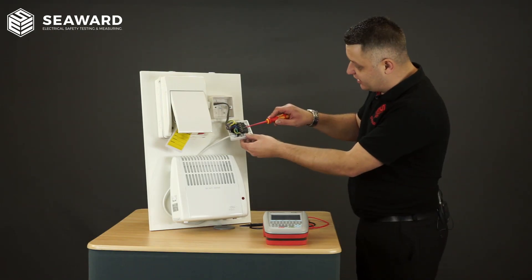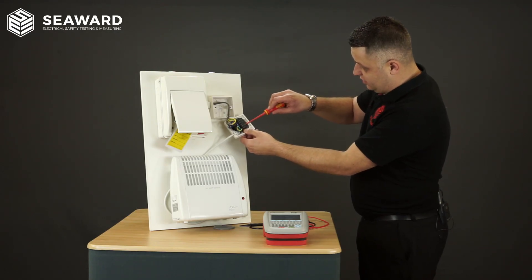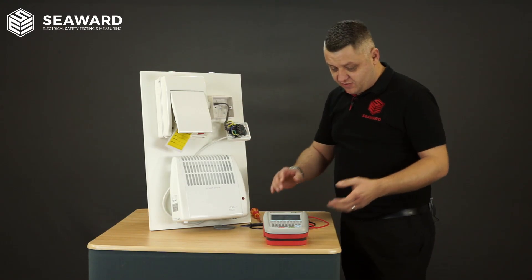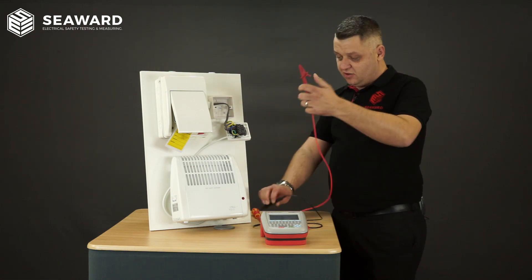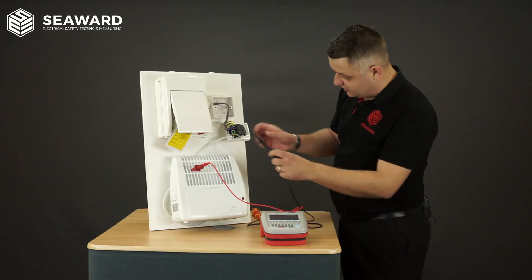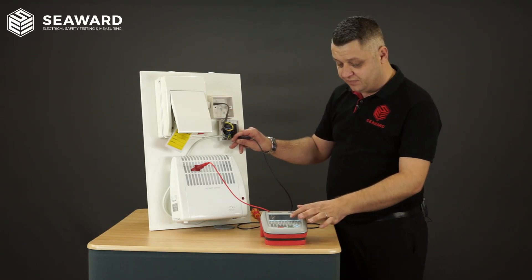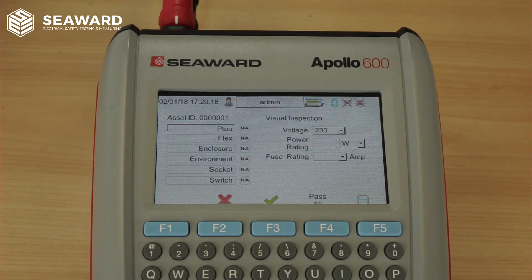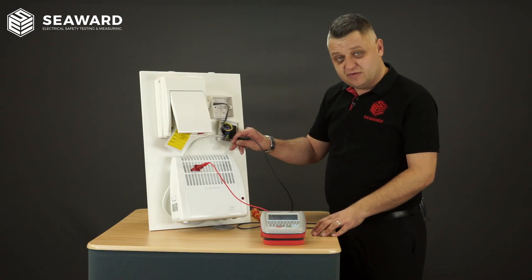To do this we will disconnect the neutral and live conductors ready for the test, but leaving the CPC connected. On the Apollo tester we have a built-in sequence for testing a fixed class one appliance. To carry out this test I'm going to apply my crocodile clip onto the exposed metal part of the appliance and the other test probe onto the earth part of the fused connection unit. When ready, the Apollo will ask me for the visual inspections so I can record that those have passed, and it will then come up with a message ensuring the equipment has been safely isolated and is ready to commence with the test.